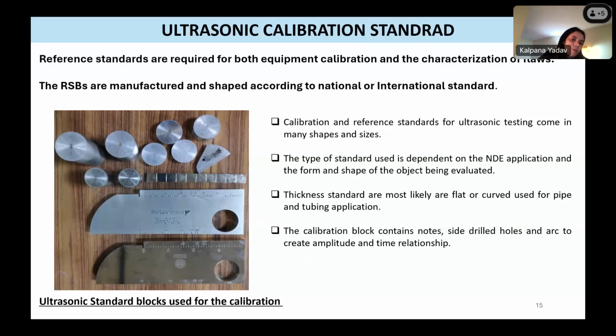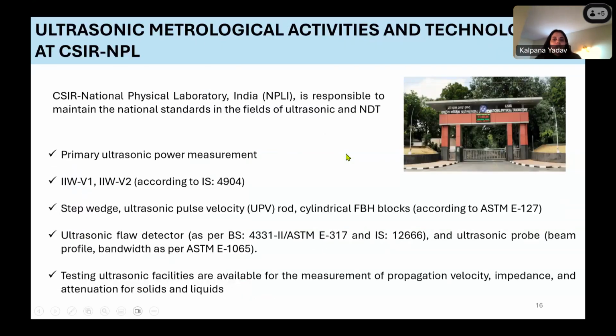In the field, you test your material, whatever you are testing. Suppose you are testing a bridge. You put your transducer on that bridge and get some signal reflected from the material, and for that you need a reference standard block. Whatever signals you are getting, you need to know whether they are in the correct form and whether the energy of the signal is the same, so you use the reference standard block to calibrate before running your actual test.